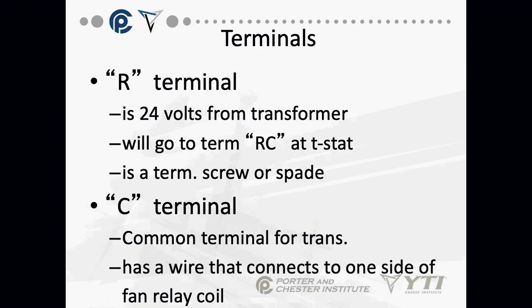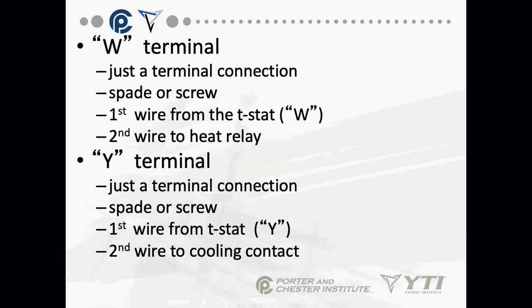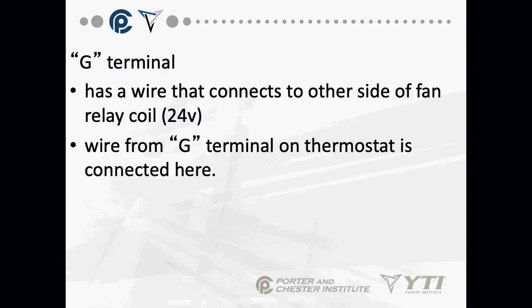The R terminal is my 24 volts from the transformer. The C terminal is the common from the transformer, and it's pre-wired to one side of the relay. It comes pre-wired, you don't have to wire anything. The W terminal is just a connection. It doesn't do anything other than allow you to connect two wires together. The same thing with the Y terminal. Again, it just allows you to connect two wires together. And the G terminal comes from the thermostat G terminal, and you connect it together. So you take the G on the thermostat, and you connect it to the G on the fan center. Hard to mess up. And the G energizes that relay.